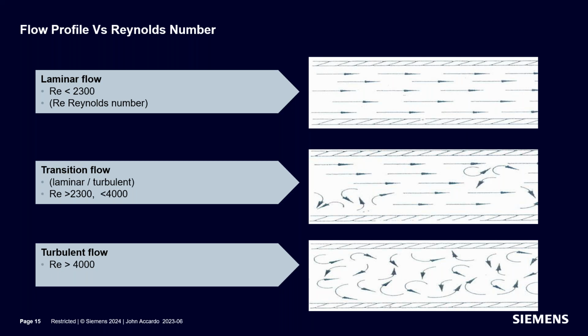But the reason I call it the dreaded transition region is because it doesn't hurt the flow meter at all, but it will impact any flow meter's accuracy because it's unpredictable. The definition of transition is there's no definition. So you really don't know how turbulent you are and how laminar you are. And so you're trying to apply a correction factor, and we do apply a correction factor in the transition region, but you don't know how perfect it is. You never really will know. So you can see a departure from your accuracy while you're in transition. And it's not ridiculous, but it could be ridiculous, but it generally isn't. It's just a couple of percent.